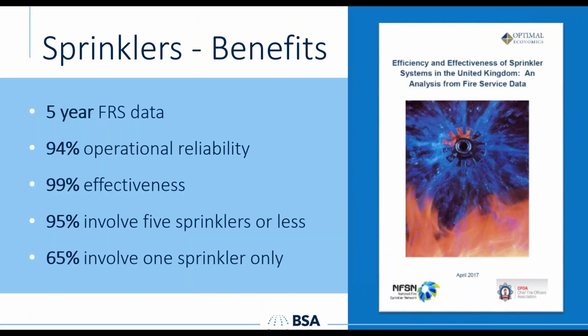There was a study done in 2017 based on fires across the UK and the recorded data about those fires where sprinklers operated. Across 5 years, it showed sprinkler systems have a 94% operational reliability, meaning 94 times out of 100 when called to operate, they operate effectively. 99% of the time when called to operate, they control or extinguish the fire. We also see that in 95% of situations, 5 sprinkler heads or less operate to control the fire, and in 65%, only 1 sprinkler head operates.